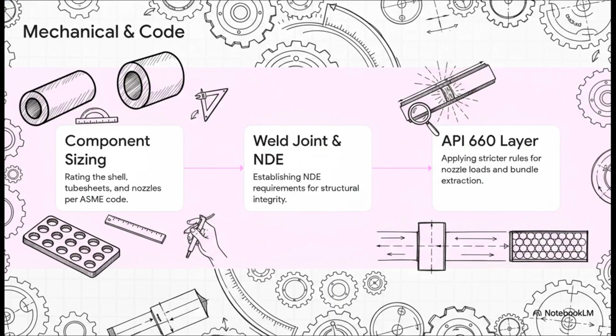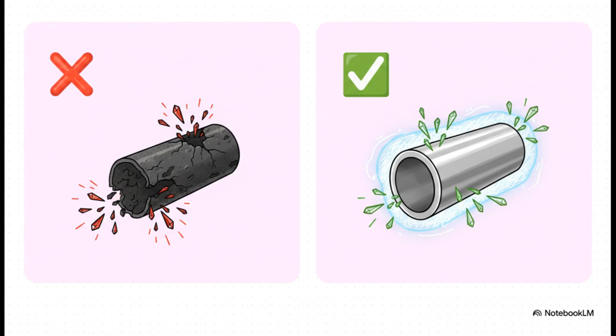Of course, a perfect design is useless if made from the wrong material. This brings us to a decision that was 100% non-negotiable for the long-term reliability of this cooler. Standard carbon steel would have been eaten alive by the acidic, chloride-heavy process fluid. The only viable option was stainless steel 316L, specifically alloyed to fight off this kind of chemical attack. It's a classic case of paying for the right material up front to avoid catastrophic failure down the road.